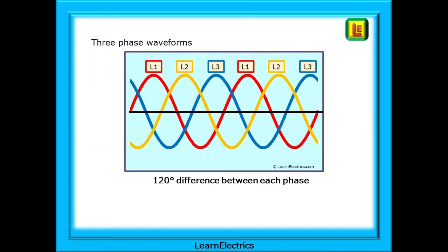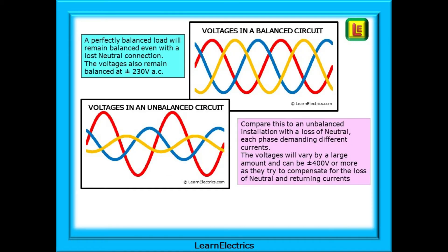A three-phase waveform is shown here. It has three cyclical waveforms, which we've called L1, L2, and L3. They are still at 50 cycles per second, but each phase is 120 degrees offset from the others. The interesting thing with a three-phase circuit is that a perfectly balanced three-phase load will remain balanced even with a lost neutral connection, and the voltages will also remain balanced at 230 volts AC.